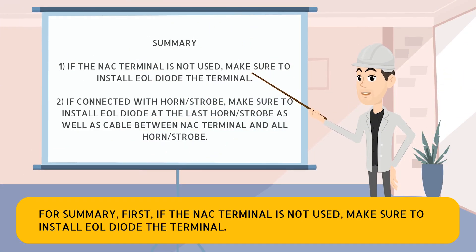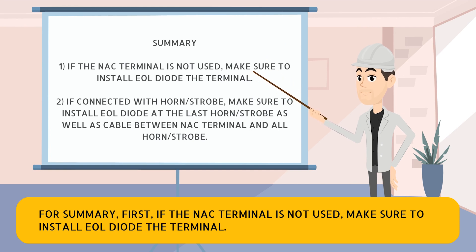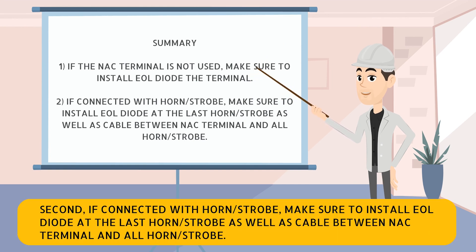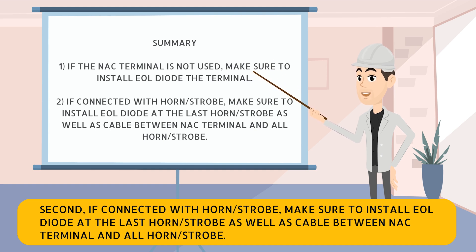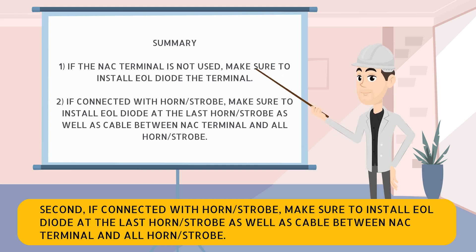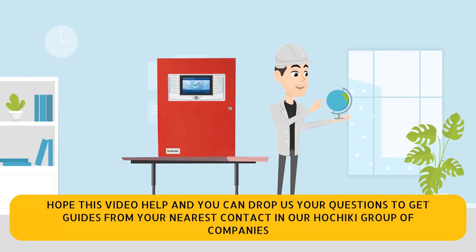For summary: first, if the NAC1 terminal is not used, make sure to install the EOL diode at the terminal. Second, if connected with a horn strobe, make sure to install the EOL diode at the last horn strobe, and ensure the cable between the NAC1 terminal and all horn strobes is intact. We hope this video helped, and you can drop us your questions to get guidance from your nearest contact in our Hochiki group of companies.